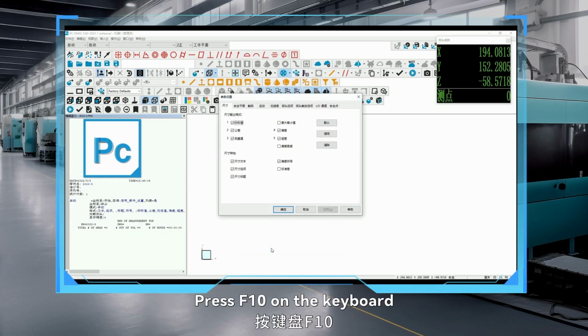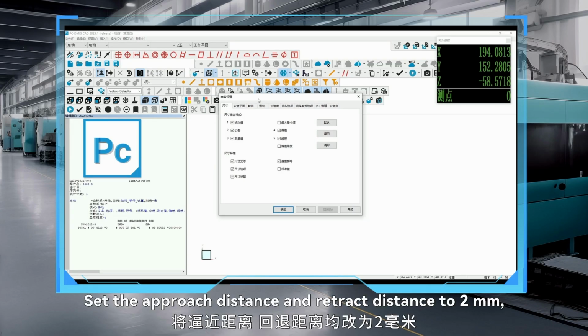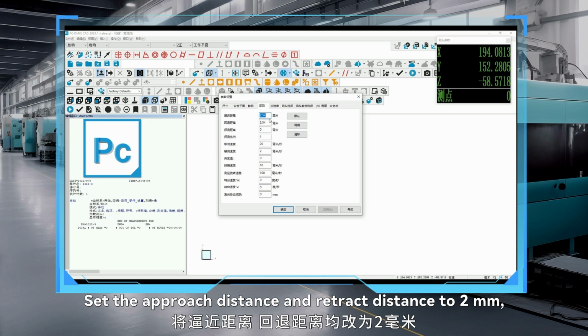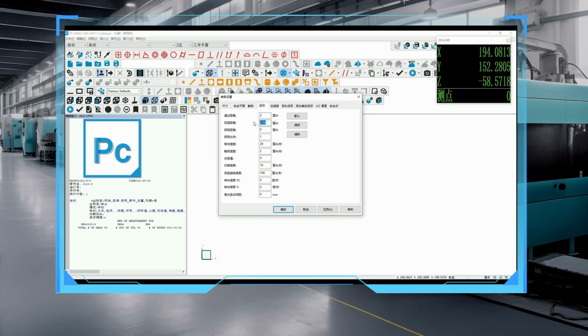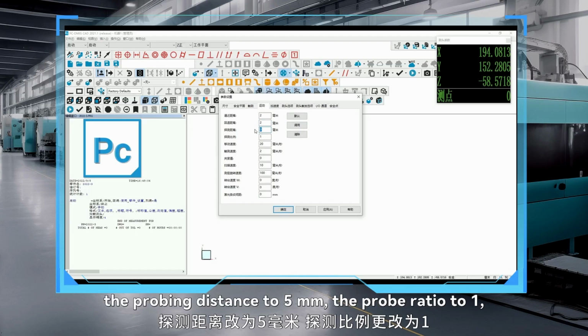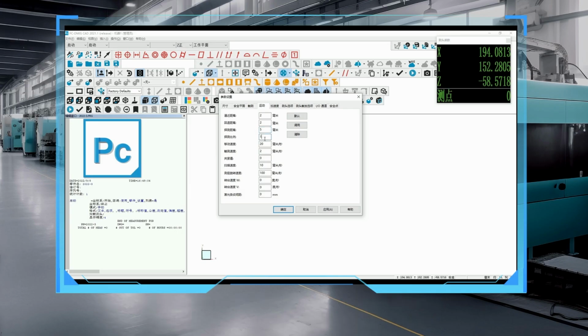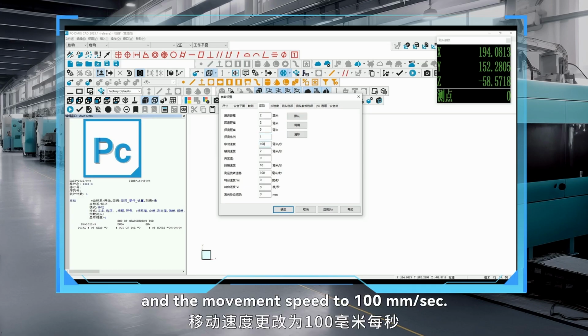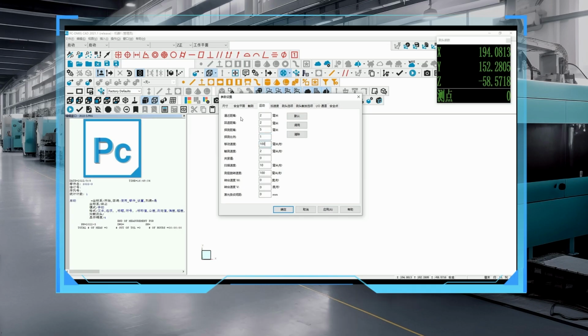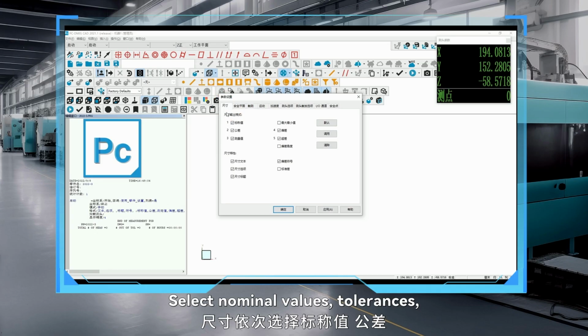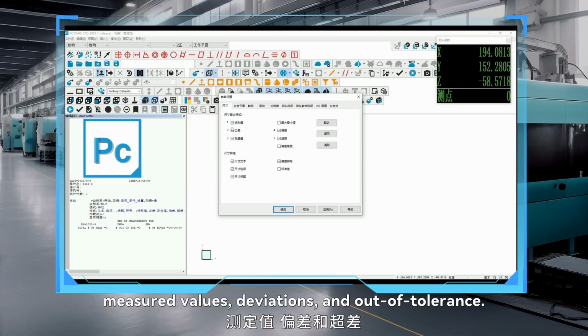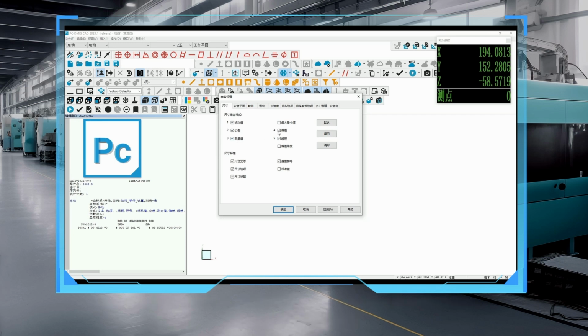Press F10 on the keyboard to enter the parameter settings menu. Set the approach distance and retract distance to 2 mm, the probing distance to 5 mm, the probe ratio to 1, and the movement speed to 100 mm per second. Select nominal values, tolerances, measured values, deviations, and out of tolerance. Click OK.